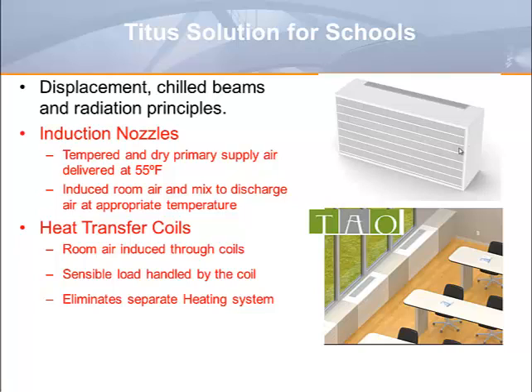The classroom is ventilated and conditioned in a displacement manner identical to that in a conventional displacement system. However, the unit also incorporates a series of induction nozzles and heat transfer coil, which allows the induction and the reconditioning of room air within the terminal.